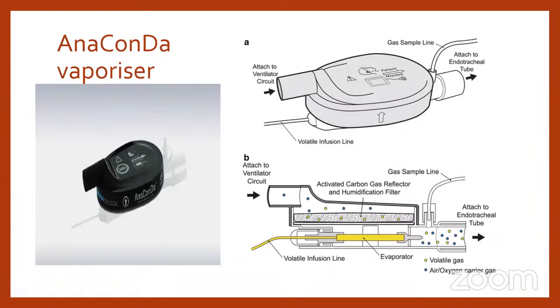Sir, Anaconda is a disposable medical device. We can keep that device in the HME filter area. That means when you are connecting the Y-piece to the ET tube, that is the place you have to connect. A special syringe pump is there, so the volatile injection is coming, and the vapor goes to the inflow. So we can monitor the exhaled flow also, and you can monitor the percentage, how much MAC value has gone. The device has a dead space of 50 ml, and even when the patient's tidal volume is 200 ml, this device will still act as the Anaconda.